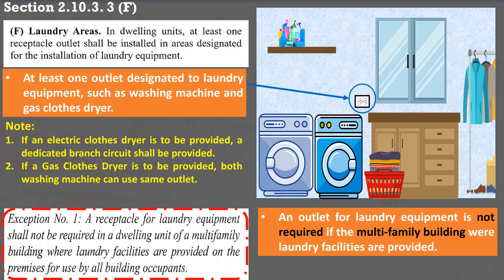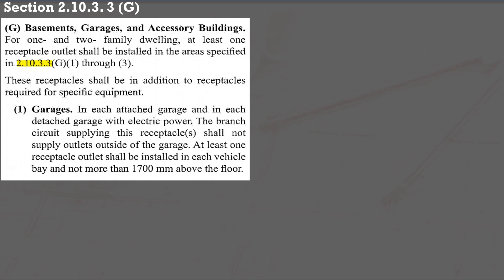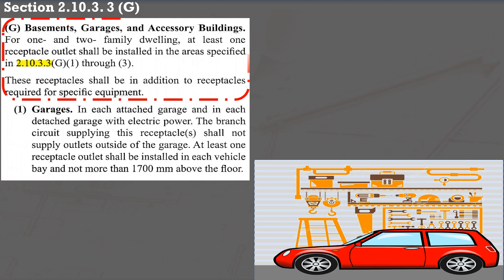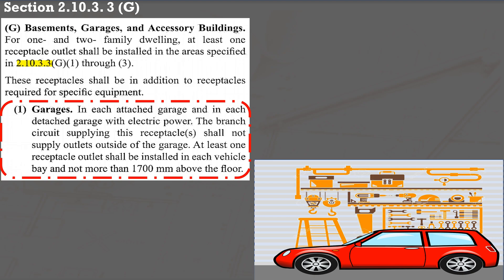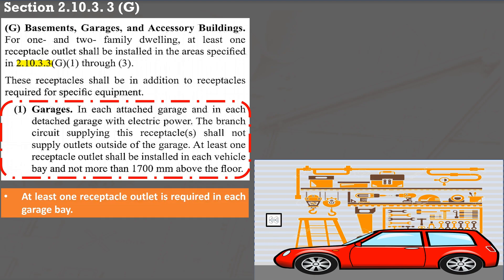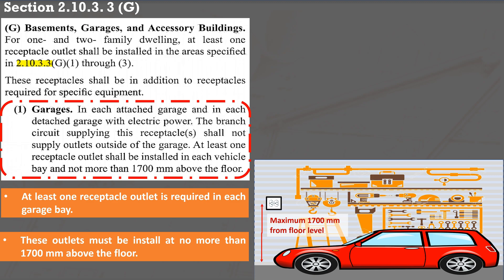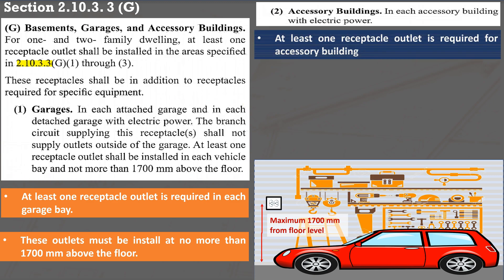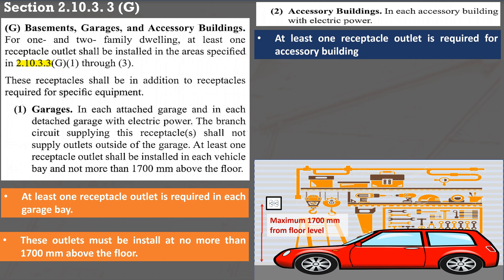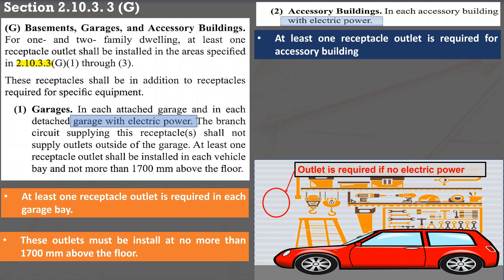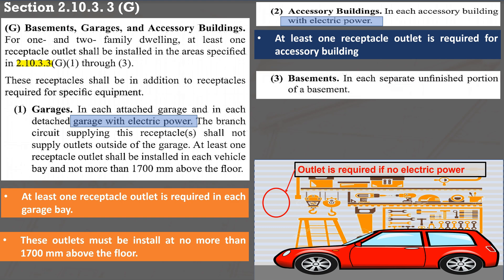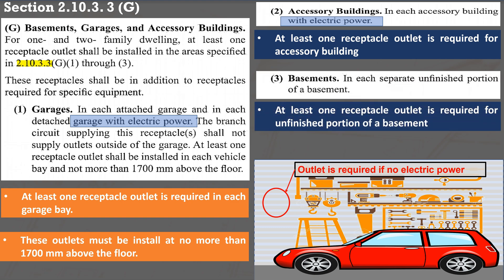At least one outlet is required for basements, garages, and accessory buildings of one- and two-family buildings as specified in section 2.10.3.3. For an attached or detached garage with electric power, an outlet shall be installed in each bay at a maximum height of 1,700 mm. For an accessory building with electric power, at least one outlet is required. If the garage or accessory building does not have an electric supply, an outlet is not required. In basements, a receptacle outlet is required in each separate unfinished portion.